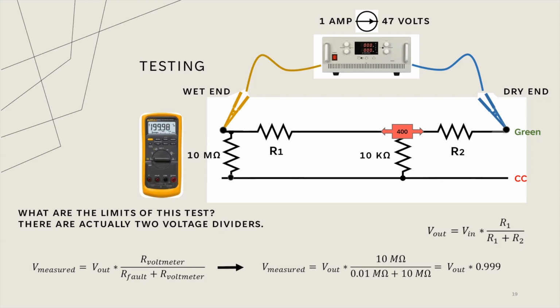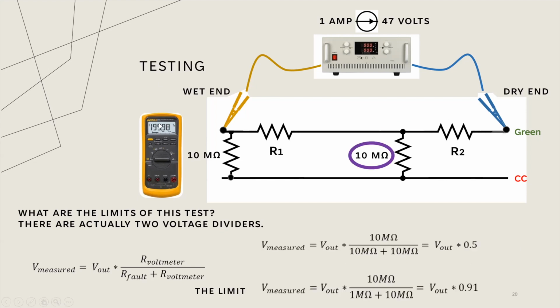But what if our fault was the same resistance as our measuring device? Well, then you would have 10 over 10 plus 10, 10 over 20. You'd be multiplying the measurement you care about to calculate your distance by 0.5. You'd have 50% error. So you're limited here to really one order of magnitude less than your measuring device. With that, you get 9% error, which is like 900 meters, and still pretty far off if you're trying to cut a cable and save as much of it as you can.